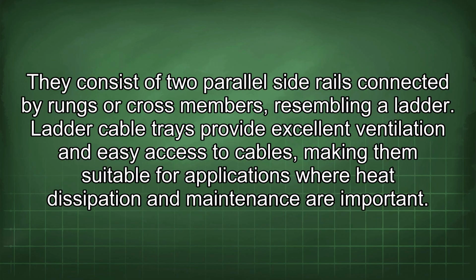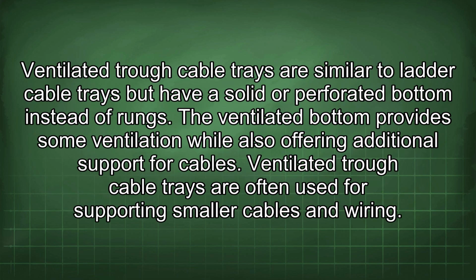They consist of two parallel side rails connected by rungs or cross members, resembling a ladder. Ladder cable trays provide excellent ventilation and easy access to cables, making them suitable for applications where heat dissipation and maintenance are important. Ventilated trough cable trays are similar to ladder cable trays but have a solid or perforated bottom instead of rungs. The ventilated bottom provides some ventilation while also offering additional support for cables.